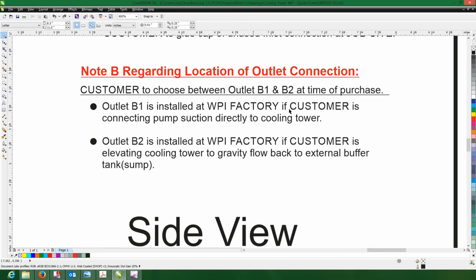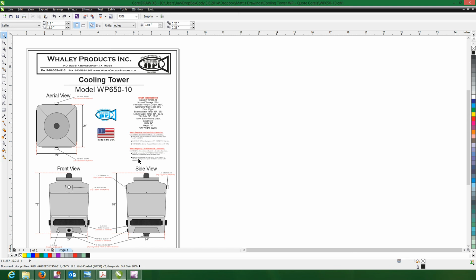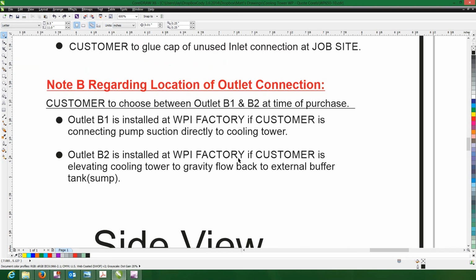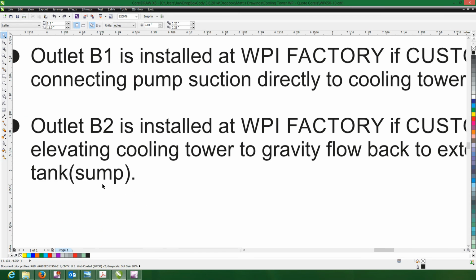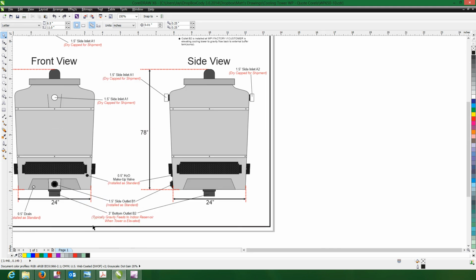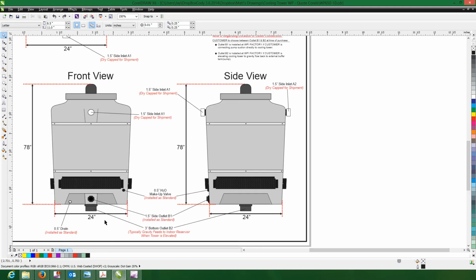But with the outlet, whenever the customer purchases, they have two options. They can either go with a side outlet, B1, if they're connecting to a pump suction directly to the tower, or B2 installed at the factory if the customer is elevating the cooling tower to gravity flow back to an external buffer tank sump. The sump is just another word for a cooling tower buffer tank. So that pretty much sums it up.